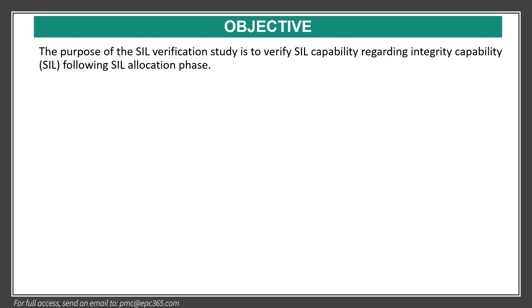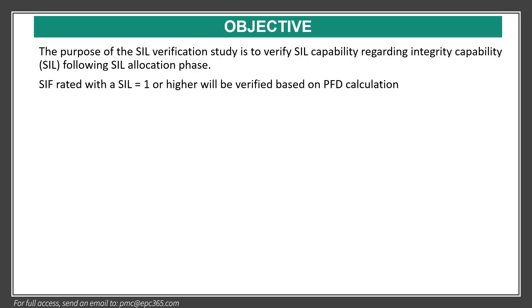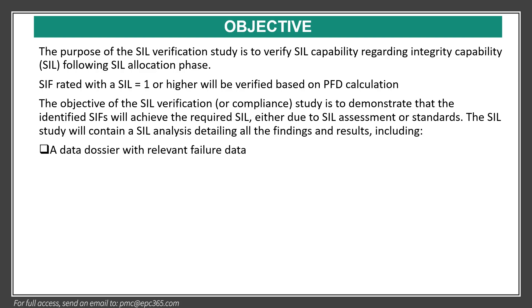What is the objective of SIL verification? The purpose of a SIL verification study is to verify SIL capability regarding integrity capability as SIL, following the SIL allocation phase. We define which SIL each loop should have, and then we verify them by SIL verification. SIFs rated SIL 1 or higher will be verified based on probability of failure on demand calculation.